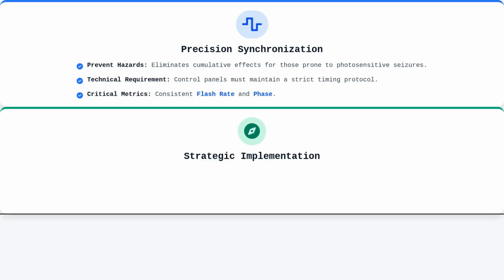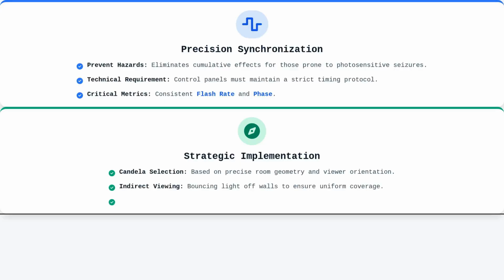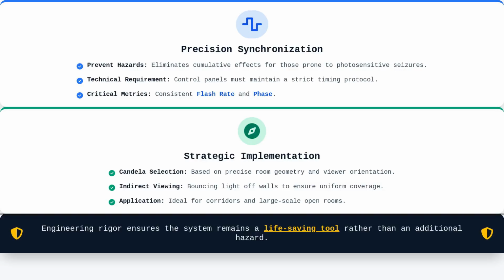Beyond synchronization, we must select candela ratings based strictly on the room geometry and the viewer's orientation to the device. Indirect viewing strategies are common in corridor or large room designs, where high-output strobes bounce light off wall surfaces to provide uniform coverage without overwhelming occupants. This engineering rigor ensures that the notification system remains a life-saving tool rather than an additional hazard during an already dangerous fire event.